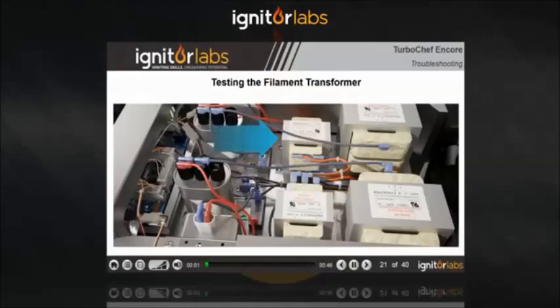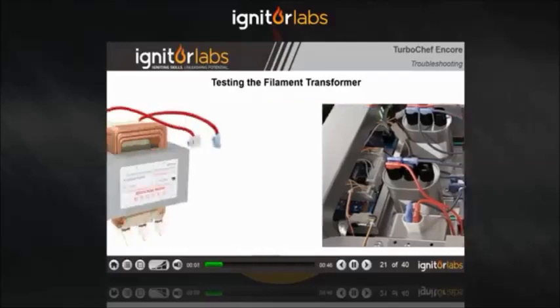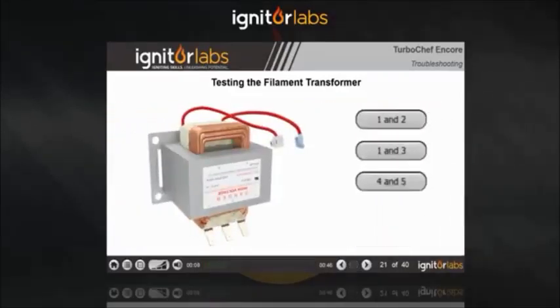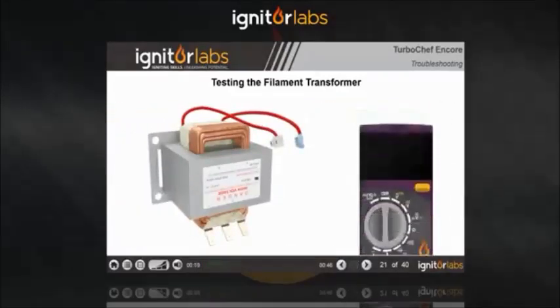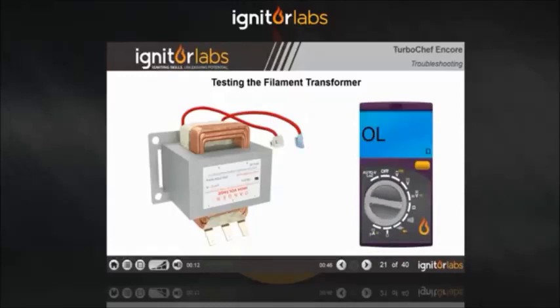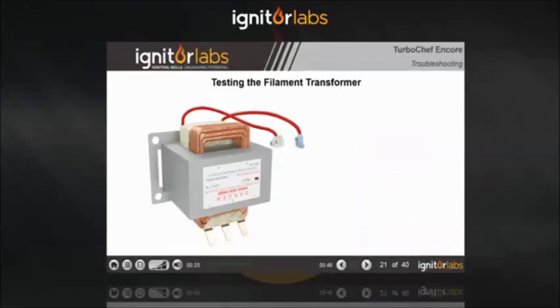Testing a filament transformer is done much like a high-voltage transformer. Note the wire positions and remove the wires. With your meter on the ohm scale, measure between terminals 1 and 2. You should see between 17.49 and 21.37 ohms.